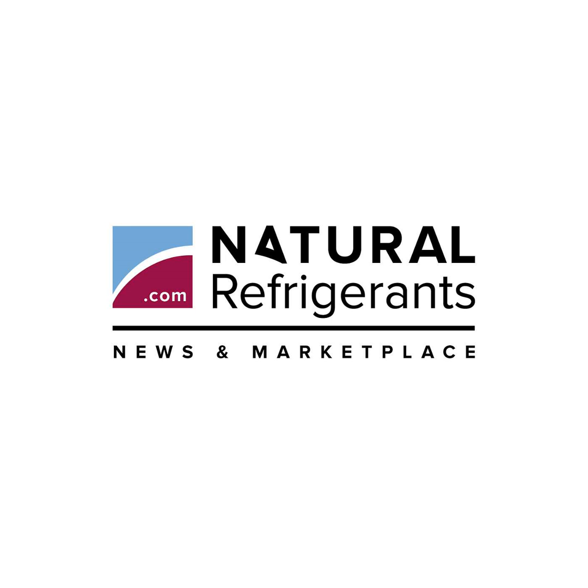In Southern California, the panels allow us to maintain operation in the peak of summer without using sprinklers on the coils, Holzschuh said. In 2026, we plan to put enough panels on the roof to remove the air-cooled condenser from the system. We reduced water usage by 40% in a Nevada store by using the panels to desuperheat an evaporative condenser, Goldstein said. Quotable: As a passive heat rejection system, the panels can be used in any application, said Holzschuh. It seems like a perfect opportunity to pair Skycool panels with a water-cooled propane system to create a more efficient process.